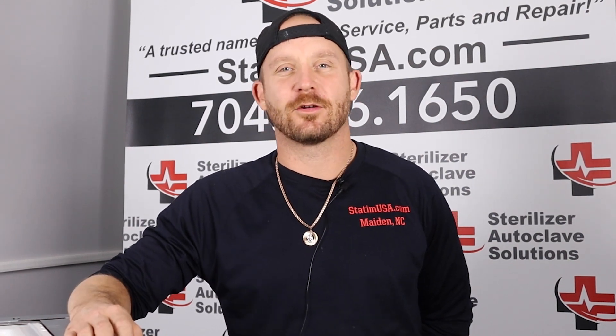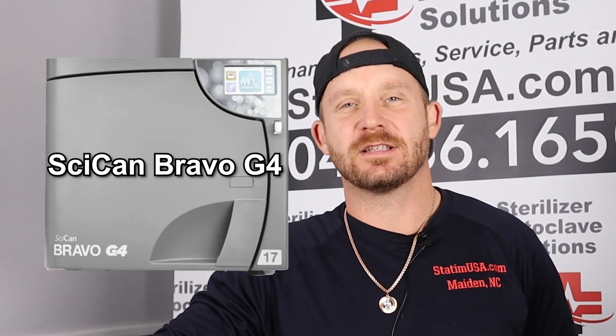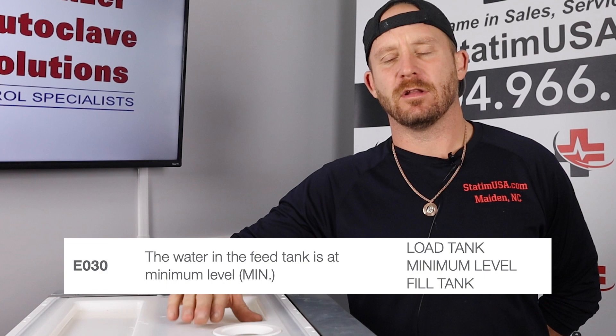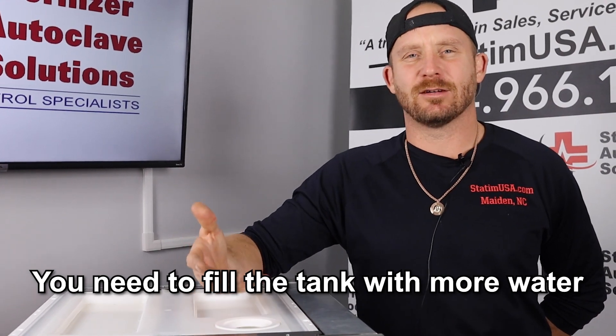Hi, I'm Andrew from Sterilizer Autoclave Solutions. We're going to go over the error codes for the SciCan Bravo G4 steam sterilizer. Right now we will discuss error code E030, which indicates that the minimum fill level in the water tank has been reached. There are a couple of floats inside your fresh water tank — this error means you are at the bare minimum of water in the tank.